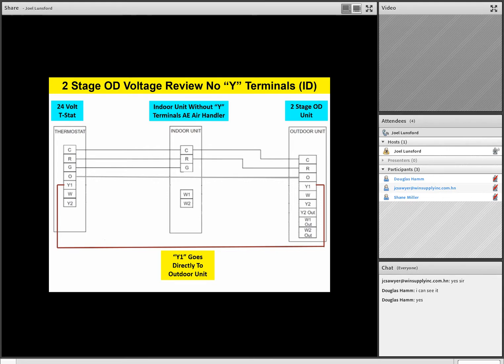We'll then take W from the thermostat directly outside, because again, we're going to allow the outdoor unit to stage first and second stage auxiliary heat on the indoor unit. And then we'll also take Y2, or second stage compressor operation, directly outside. So those three terminals, they don't even touch the air handler. Y1, W, and Y2, they don't even go to the air handler. They go directly outside. Are there any questions or comments so far?